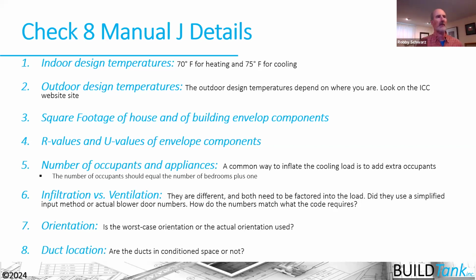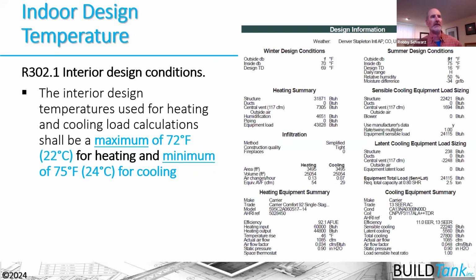So let's begin with number one and talk about the interior design temperatures. The interior design temperatures are actually defined by the IECC, the energy code. It says that a maximum of 72 shall be used for heating season and a minimum of 75 for cooling season. So when we look at our HVAC design, we'll get a design information report, and we can see that the inside dry bulb temperature is 70 degrees in the wintertime, and 75 degrees in the summertime conditions.